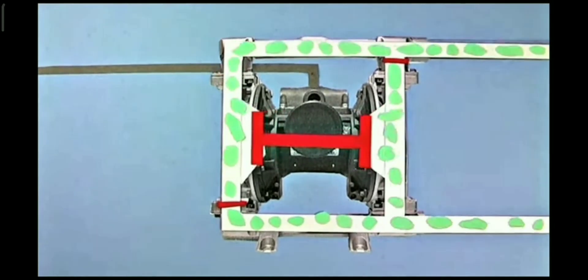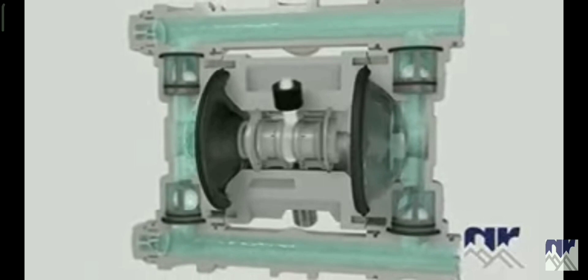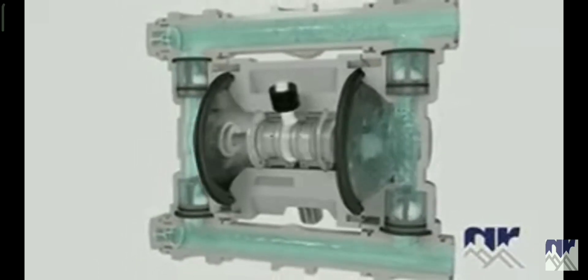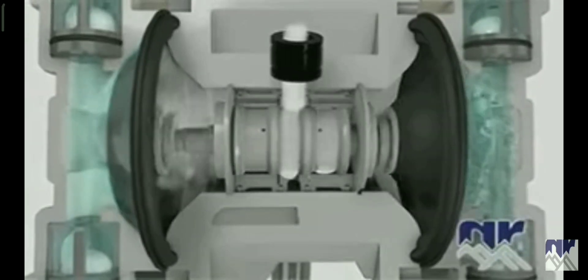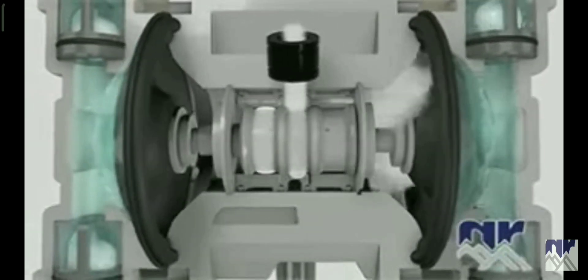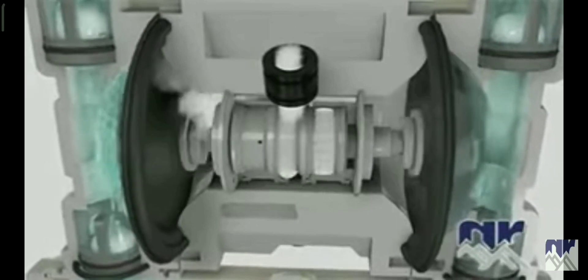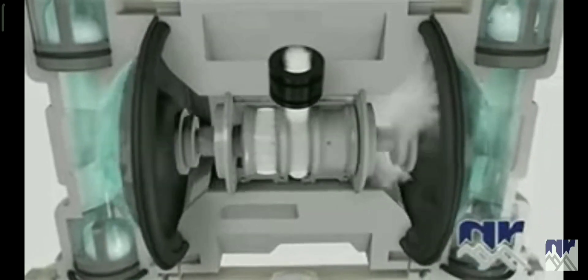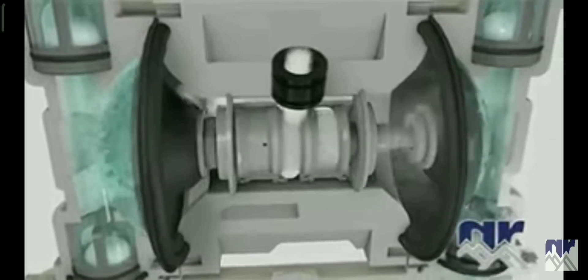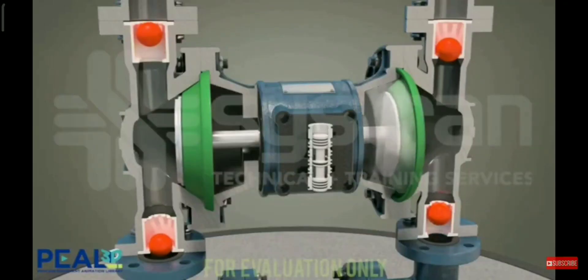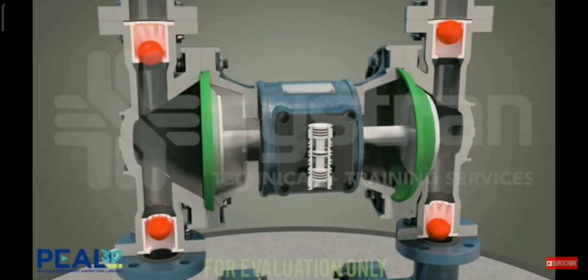Fluid enters at the inlet, which is the suction manifold. At the middle of the pump, compressed air is released which helps the diaphragm to move forward and accelerate the flow of fluid. When the air is released, the diaphragm comes back, helping fluid flow into the fluid chamber. Then the diaphragm moves forward again, pushing fluid upward and out through the delivery manifold. Valves at both the inlet and outlet allow fluid to enter and exit the pump chamber.